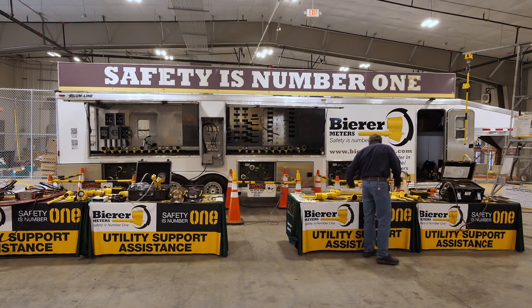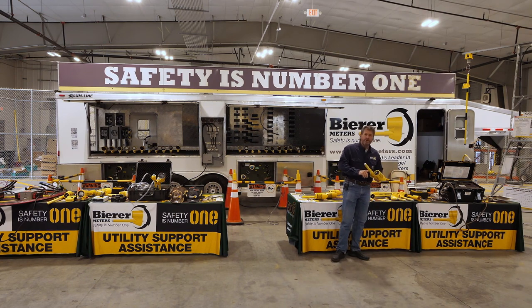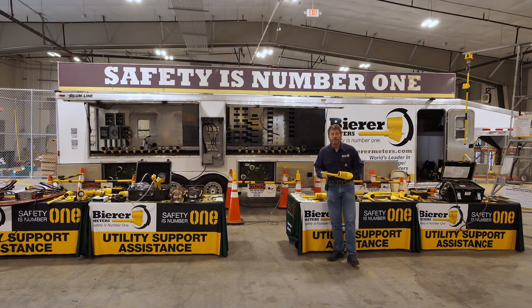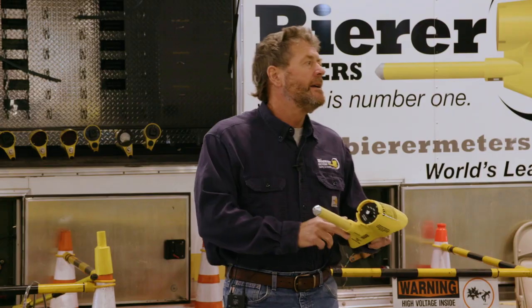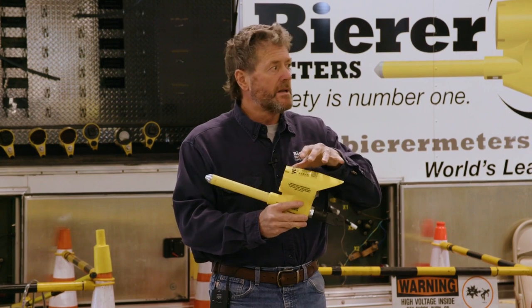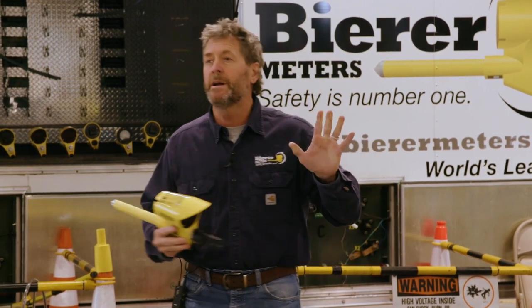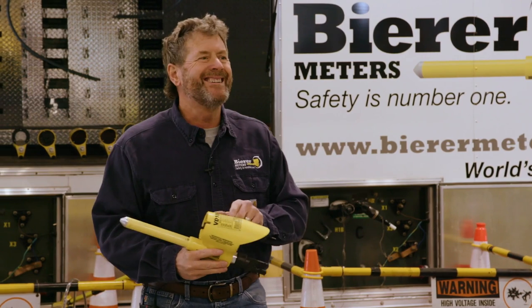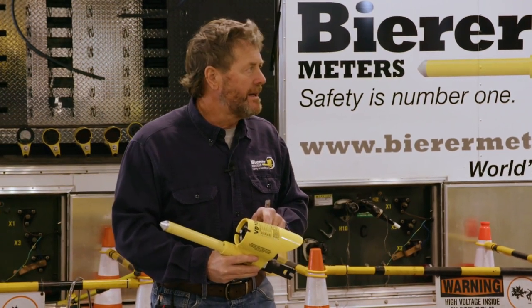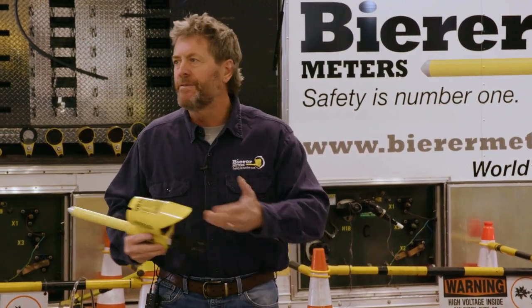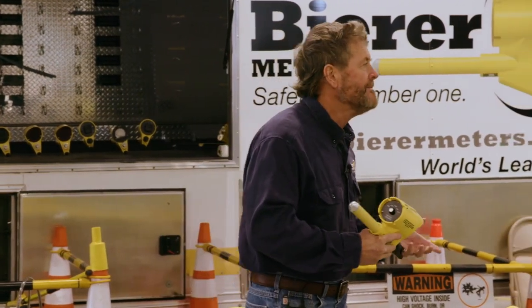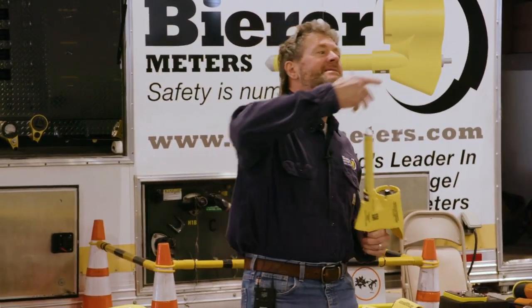So on care, you want to make sure your probes are clean. Hot stick wipes work great. No markings, no calibration stickers, no grease, no dirt, so that way you alleviate any exterior tracking to the tool, the components. The components that make the tools work, everybody's tools, are conductive. They have to be, right? In order to give you a voltage indication when you're phasing, or phase to ground, or whatever, it must be energized to give you the voltage, right?